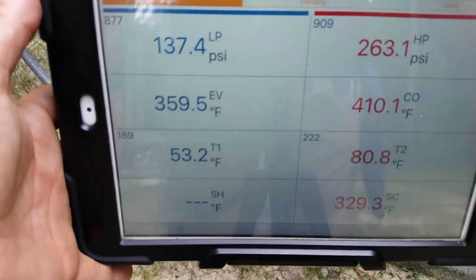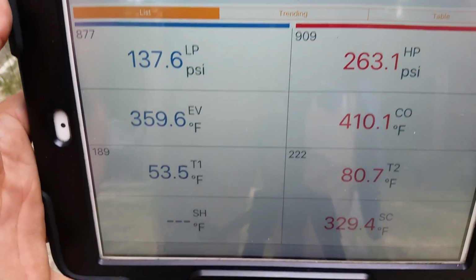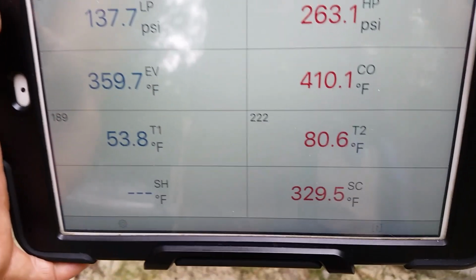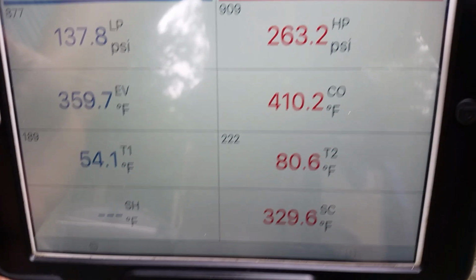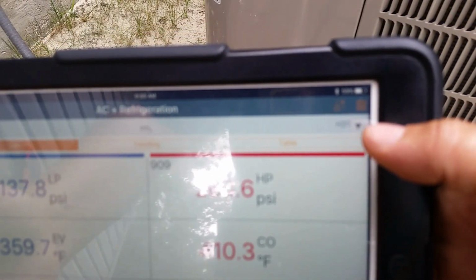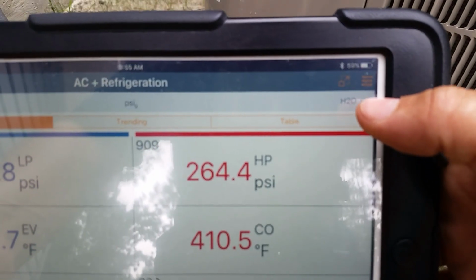Now that our probes are hooked up, we can go back to the tablet and you can see our pressures and everything on there. And as you can see, we have a crazy amount of superheat, and that's only because if you look up in this top corner, hopefully the camera will focus, you can see it says H2O.